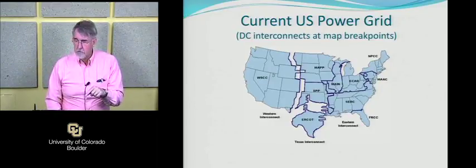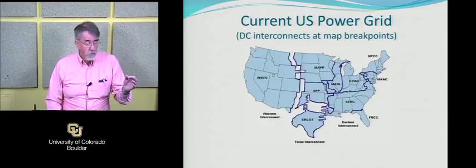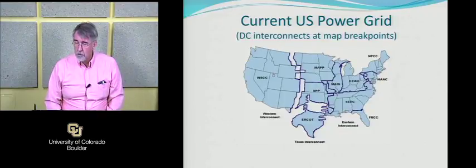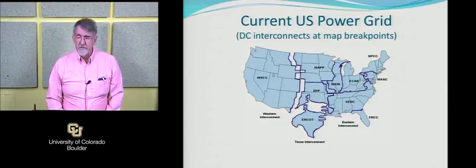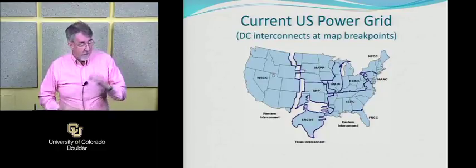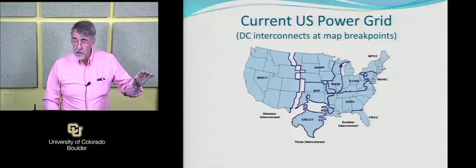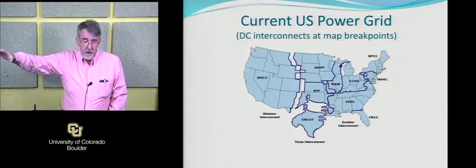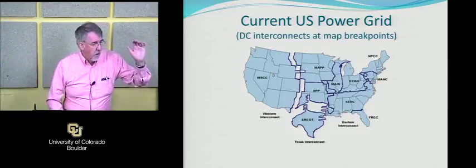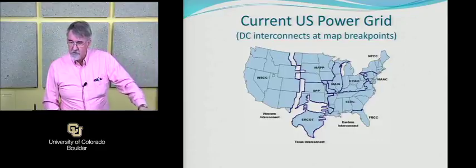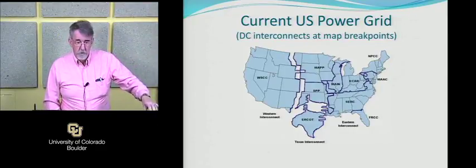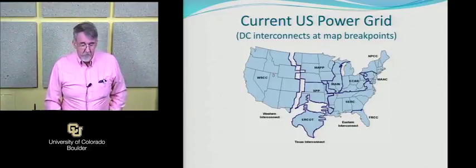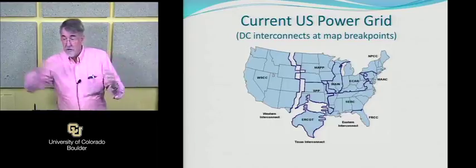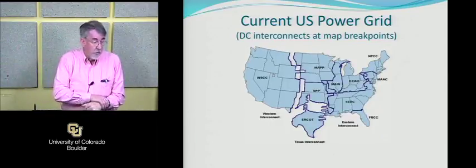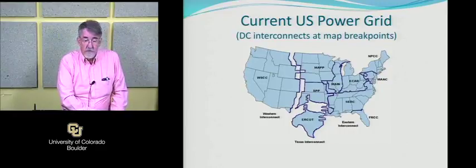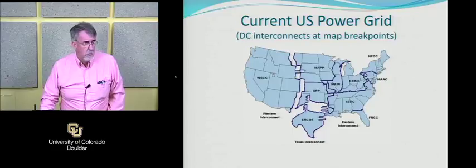Why do you think they do that? I mean, it's not long distance. Is that a way that if one screws up, it'll prevent as much effect on the other? Yes, it's to isolate them. So if you have a cascading failure in one area, it won't cascade through the DC interconnects. Failures tend to be that the frequency gets out of control; you get frequency collapse or voltage collapse, those are the things that cause instability. Frequency problems in one area aren't going to transfer to another, and even voltage problems, the interconnects are going to take care of that. So it's for isolation. Questions on that?